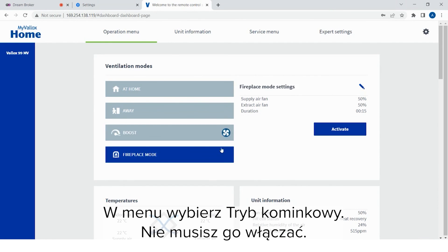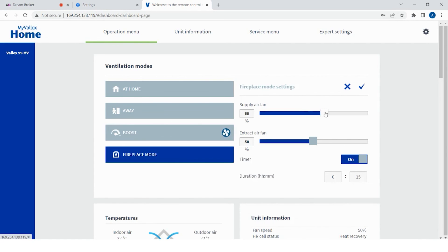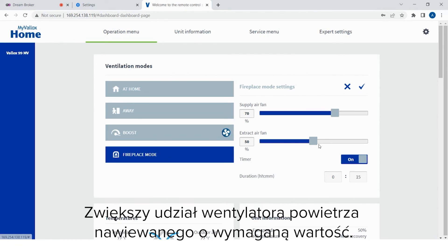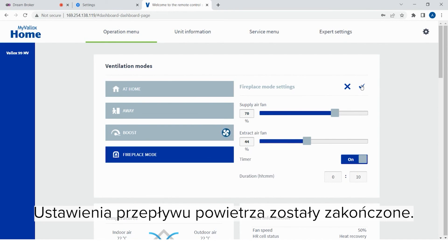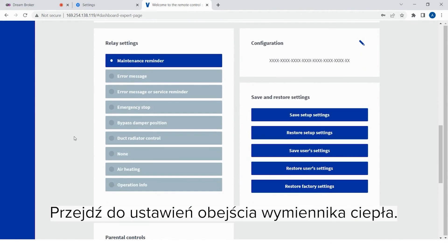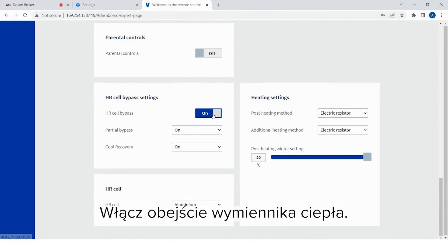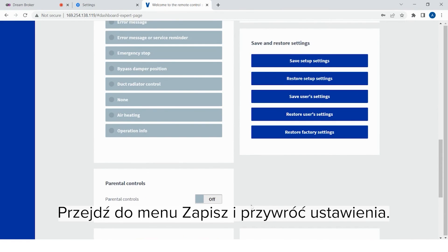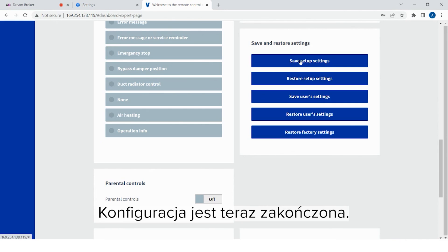Select fireplace in the menu. Set the efficiency of the extract air fan to the same level as in the at-home mode. Increase the percentage of the supply air fan by the required amount. Ensure that the timer is turned on and check its duration. If there is no fireplace in the apartment, use the same fan percentages as in the at-home mode. Air flow settings are now complete. Go to expert settings. Go to the bypass settings of the heat recovery cell. Turn on the heat recovery cell bypass. Go to the save and restore settings menu. Save the setup settings. The setup is now complete.